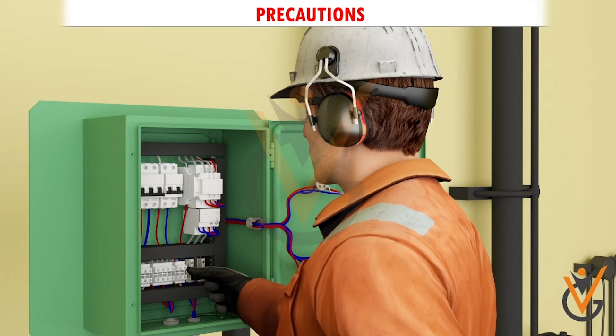Inform the duty engineer before commencing work. Fuses should be removed or circuit breakers opened to ensure that all related circuits are dead. If possible, switches and circuit breakers should be locked open, or alternatively a not-to-be-closed notice attached.